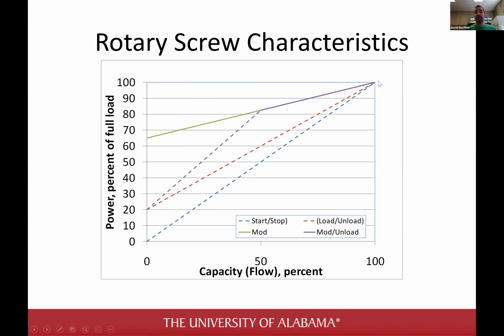No matter what control strategy you have, if you are delivering the max amount of air that the compressor can handle, it doesn't matter what you're doing. The motor is just going to be running full out the whole time, and your control strategy doesn't matter.